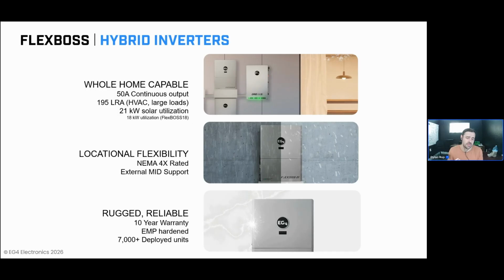Now, despite housing a host of high-powered power electronics in the system that do deliver that power capability, this is an incredibly reliable and rugged unit. First and foremost, it's designed to be deployed in just about any environmental set of conditions, with a NEMA 4X rating on the actual enclosure itself and a temperature range that enables it to be deployed down to -4 degrees Fahrenheit up to 131 degrees Fahrenheit. So just about any location is available for deployment.